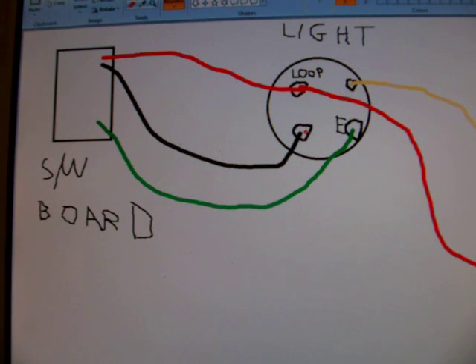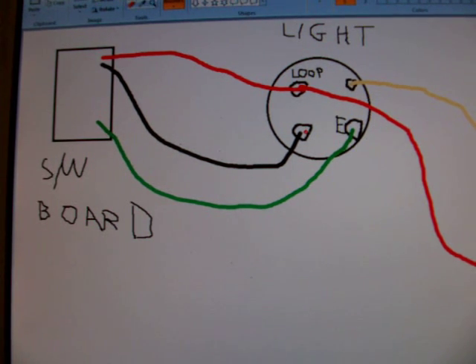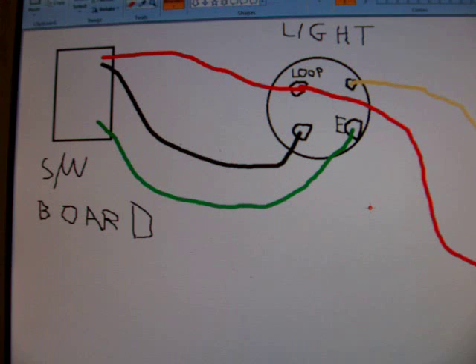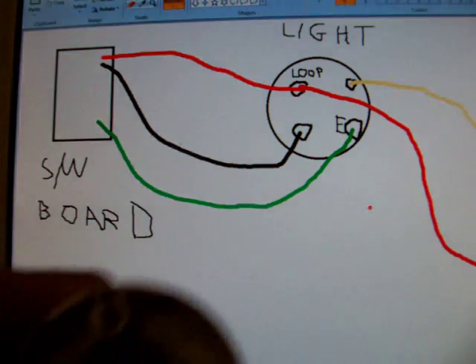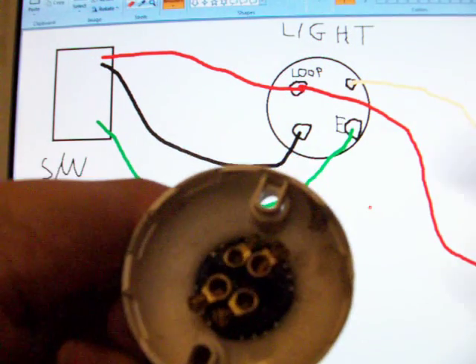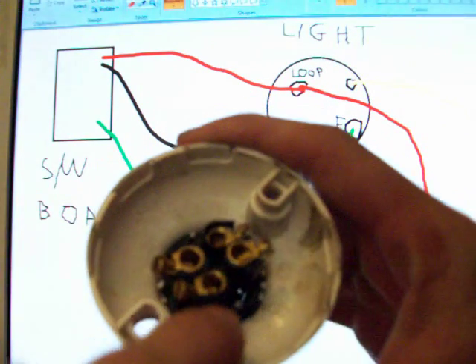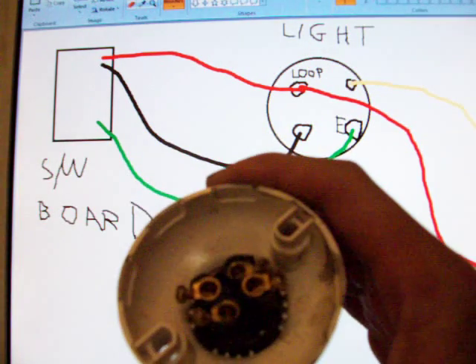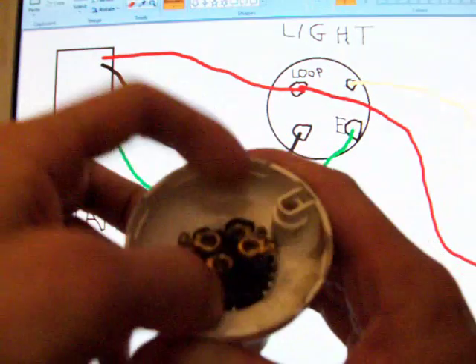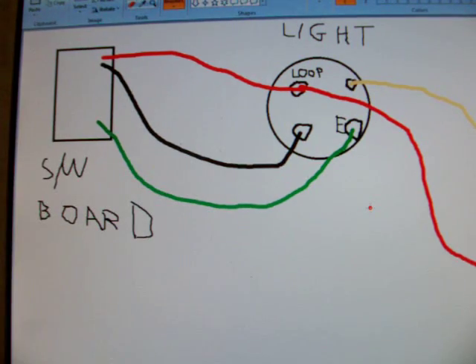When you turn a batten fix light fixture over, you're presented with four terminals. You have two unlabeled terminals. You have one called loop or L, and you've got one called E for earth. Now, technically, this is a double insulated light fixture. It can't be earthed, but it has a position. It has a position for the earth terminal. And what you're going to notice is that the loop terminal and the earth terminal are the higher of the four terminals. And they're all sort of at slightly different levels. I'm not exactly sure why that is.